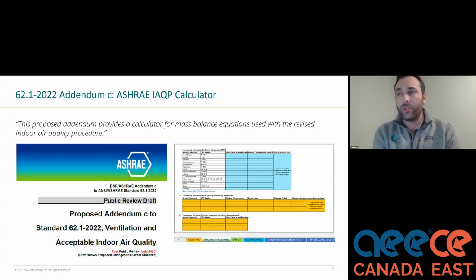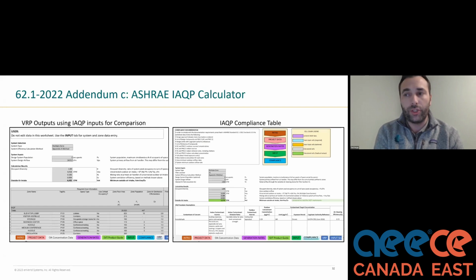But to make it easy, you don't have to build your own calculator. Here's addendum C. The calculator already has preloaded each of the design limits for each of the design compounds based on space type. All you need to do, and Inverid's already done this for you, is plug in a device efficiency. And then it's the same inputs that you use for the ventilation rate procedure. What is your occupancy? What is your square footage? And what is the system efficiency? 0.8, 1.0. And this gives you your minimum outside air requirement, as well as how much air cleaning needs to be done with a device of that efficiency on each of the design contaminants. As I mentioned before, formaldehyde is typically what drives these IAQp calculations.